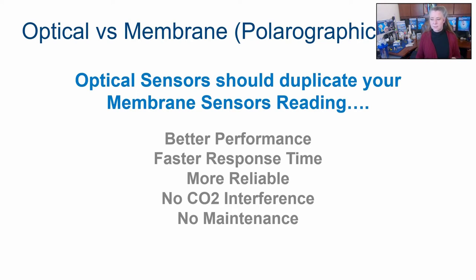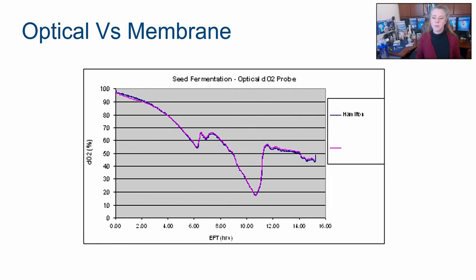There are two places, however, where polarographic probes will give you different performance than optical. And I'm going to give you these examples. In this example, the blue line is a Hamilton optical probe and the purple line is a polarographic probe. It's a seed fermentation, and this is around 16 hours. You can see they line up really well. For context, this is in a large 15,000 liter vessel. This is exactly what you'd hope to see.